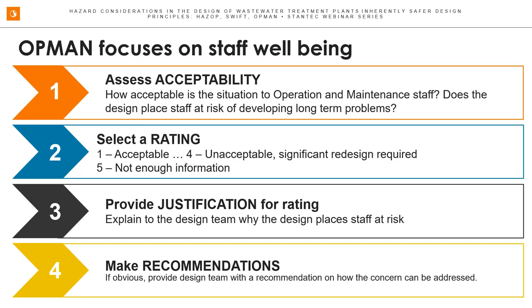So there's a worksheet that's pre-populated before the meeting from the P&ID. So every valve, etc., is listed on the workbook. You can see, for example, a manual isolation valve listed. And then there's a drop-down menu for each of them: acceptable, acceptable could be improved, unacceptable, unacceptable requires redesign, insufficient information.